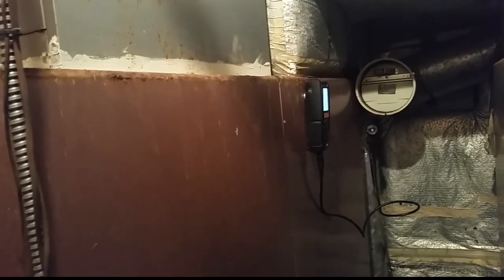One thing that I learned from Steve Lab is that sometimes people push these buttons over and over again and there'll be some raw oil in the heat exchanger. You have to let it burn off, which is a good idea because it was literally burning without the thing running. So I burned off the rest of that oil, which can be a little bit of a dangerous situation, it looks like. Because I know learning on the job is number one. But some of these people that hit these buttons over and over again, I can see how that could be a very dangerous situation for the guy coming in to take a look at it.